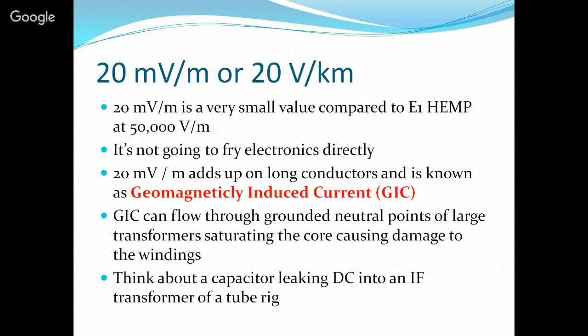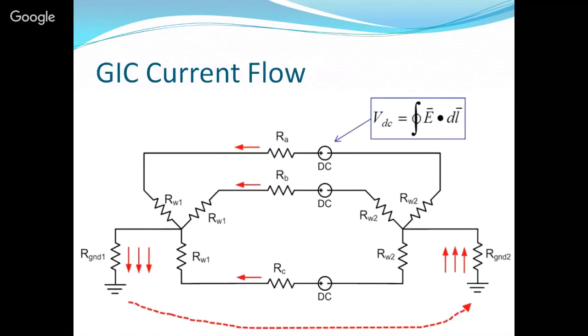But it does add up on long conductors, and it's a real problem for the electric power companies and the power grid. The main reason is because all these large transformers at substations are auto transformers. They have this center tap neutral, and you can get what's called geomagnetic induced current, which flows through the earth in one direction and then returns back through that neutral star point in those transformers, and it saturates the transformers.